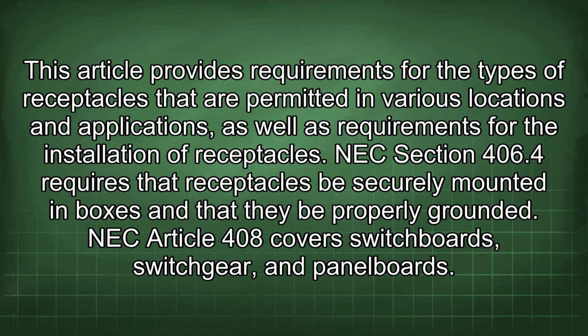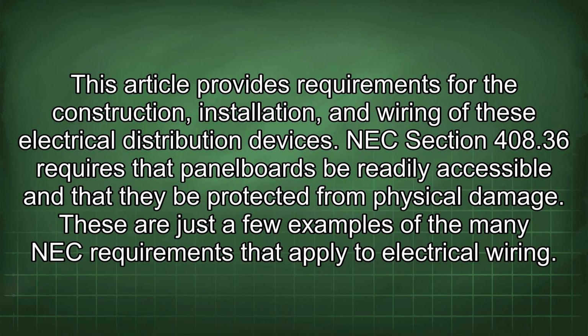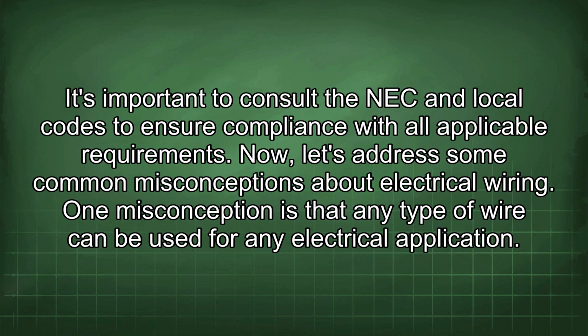NEC Article 408 covers switchboards, switchgear, and panelboards. This article provides requirements for the construction, installation, and wiring of these electrical distribution devices. NEC Section 408.36 requires that panelboards be readily accessible and that they be protected from physical damage. These are just a few examples of the many NEC requirements that apply to electrical wiring. It's important to consult the NEC and local codes to ensure compliance with all applicable requirements.